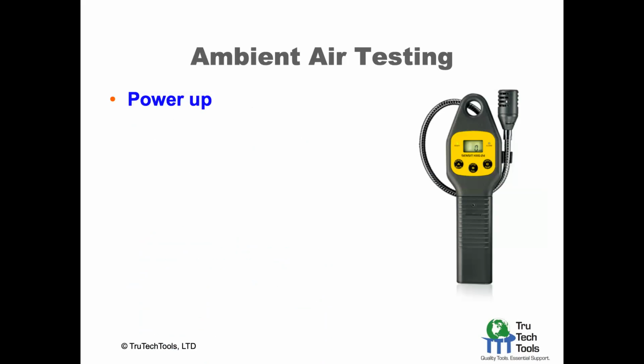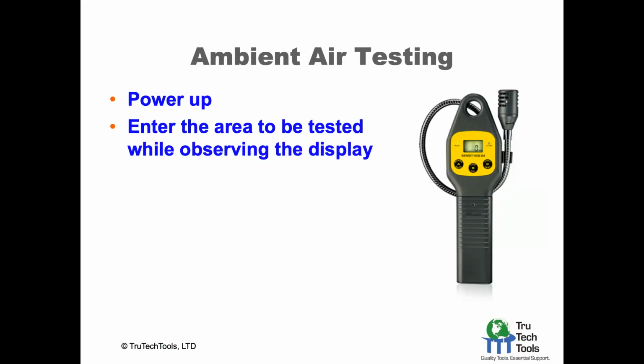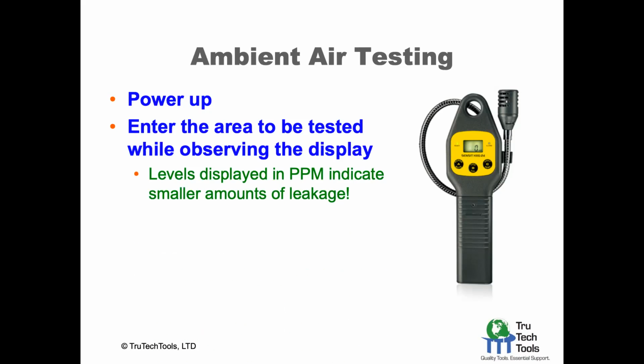To do ambient air testing, and this would be sort of your investigation standpoint, you would power up the product, as we talked about. You power up before you enter the area to be tested, and you observe the display. Of course, it'll have the audible on it, but you just want to see what's happening with the concentration as you move into this area. Levels indicated in parts per million are smaller amounts of leakage. So when you take a good hard look at the screen, is it reading ppm or LEL? ppm means it's tiny amounts. LEL means it's much larger amounts.